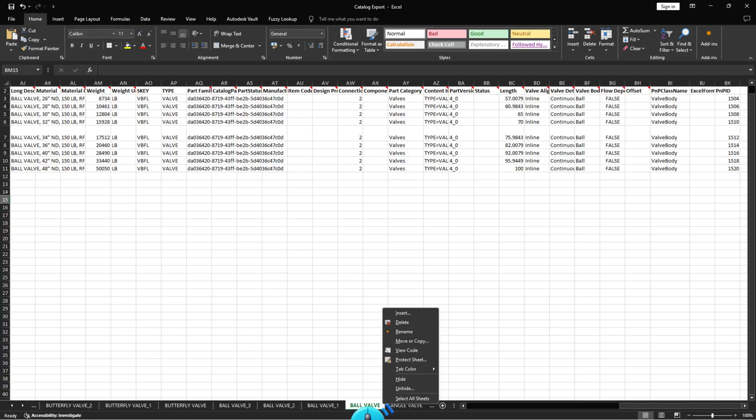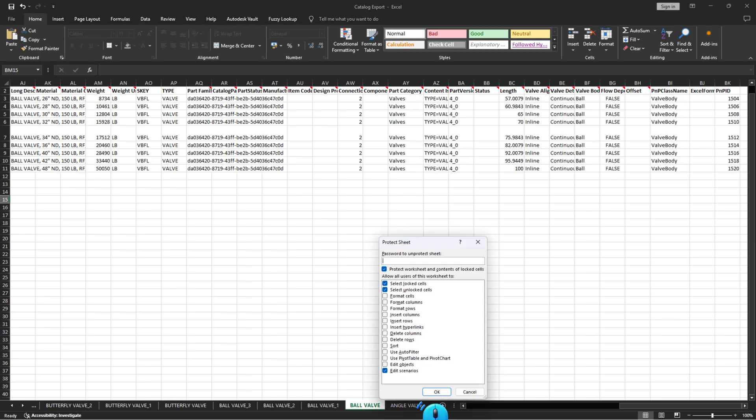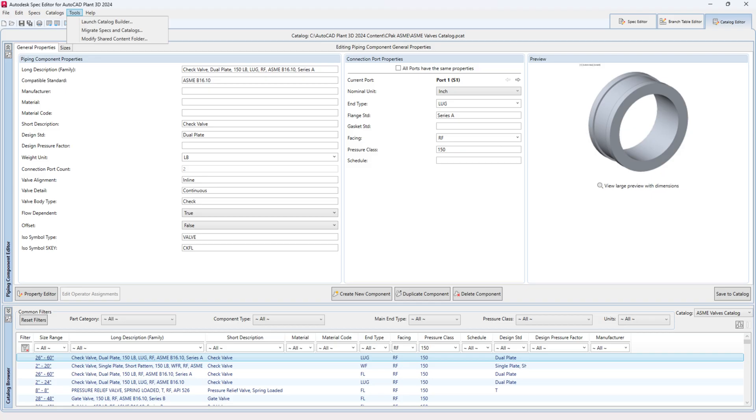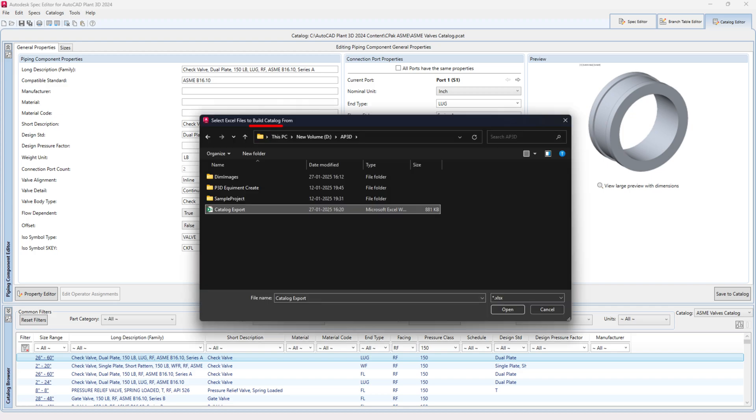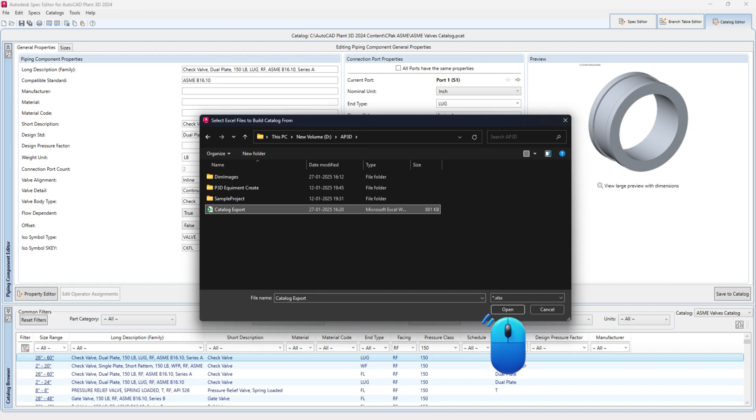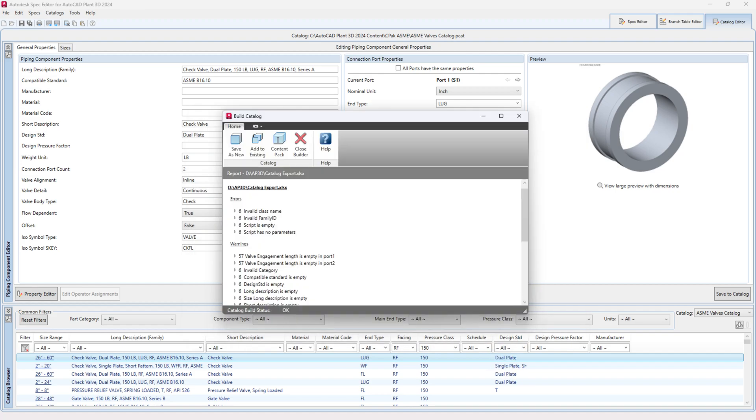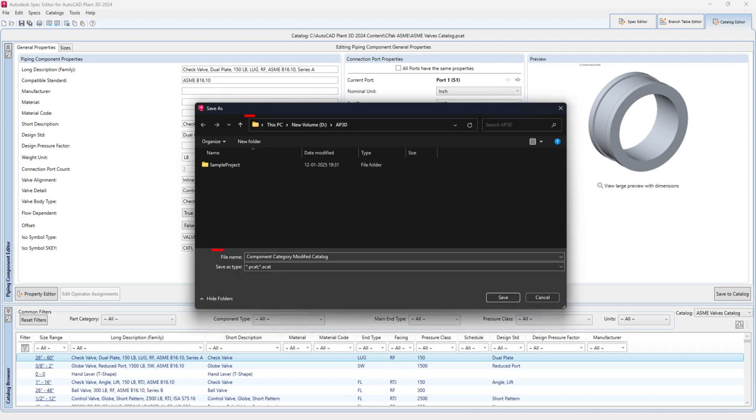Now, right-click the same tab and select Protect Sheet. Switch back to the Spec Editor for Plant 3D application. Go to the Tools tab and select Launch Catalog Builder. Click Build Catalog. Browse and select the modified Excel file. Click the Open button. If you want to save it as a new catalog, click Save as New and name the catalog. Then click Save.